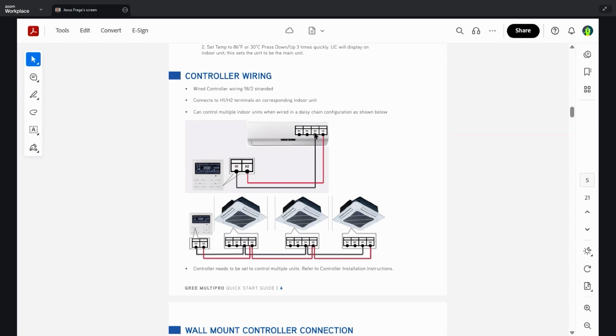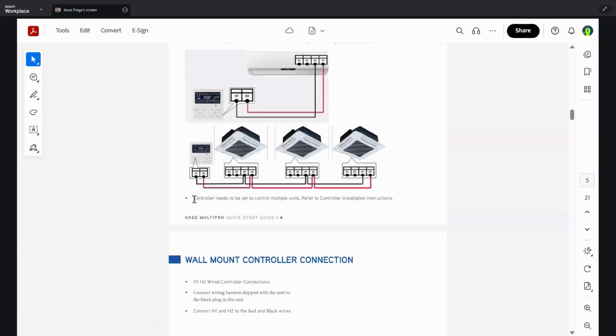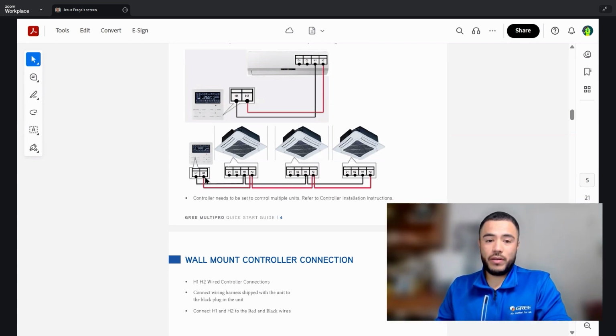And we also have another set of pins here, H1 and H2, which we know is our wired controller. So we open up this case and we'll see this terminal block there next to the line voltage terminal block. Another key feature here is if you wanted to control multiple units using one wired controller, you can also do this via daisy chaining the thermostat terminal block H1 and H2 via indoor unit to indoor unit to indoor unit.